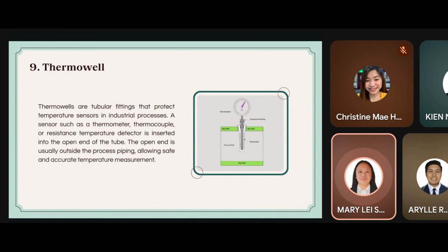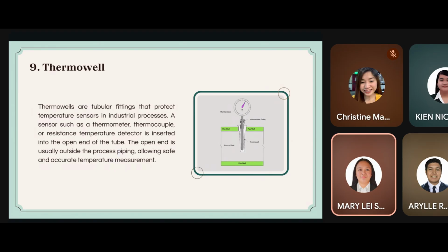We have also thermowell. Thermowells are tubular fittings that protect temperature sensors in industrial processes. A sensor such as a thermometer, thermocouple, or resistance temperature detector is inserted into the open end of the tube. The open end is usually outside the process piping, which allows safe and accurate temperature measurement.